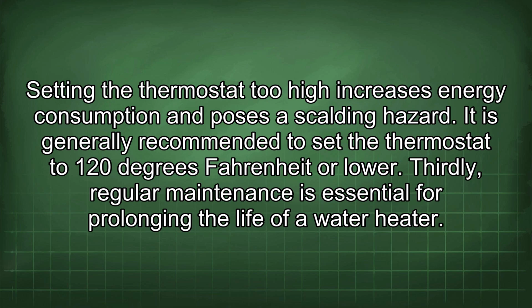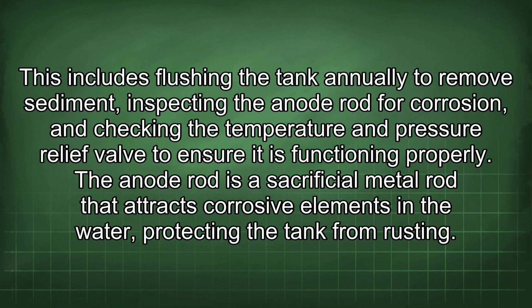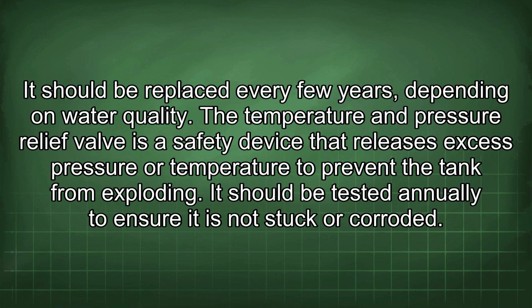Thirdly, regular maintenance is essential for prolonging the life of a water heater. This includes flushing the tank annually to remove sediment, inspecting the anode rod for corrosion, and checking the temperature and pressure relief valve to ensure it is functioning properly. The anode rod is a sacrificial metal rod that attracts corrosive elements in the water, protecting the tank from rusting. It should be replaced every few years, depending on water quality. The temperature and pressure relief valve is a safety device that releases excess pressure or temperature to prevent the tank from exploding. It should be tested annually to ensure it is not stuck or corroded.